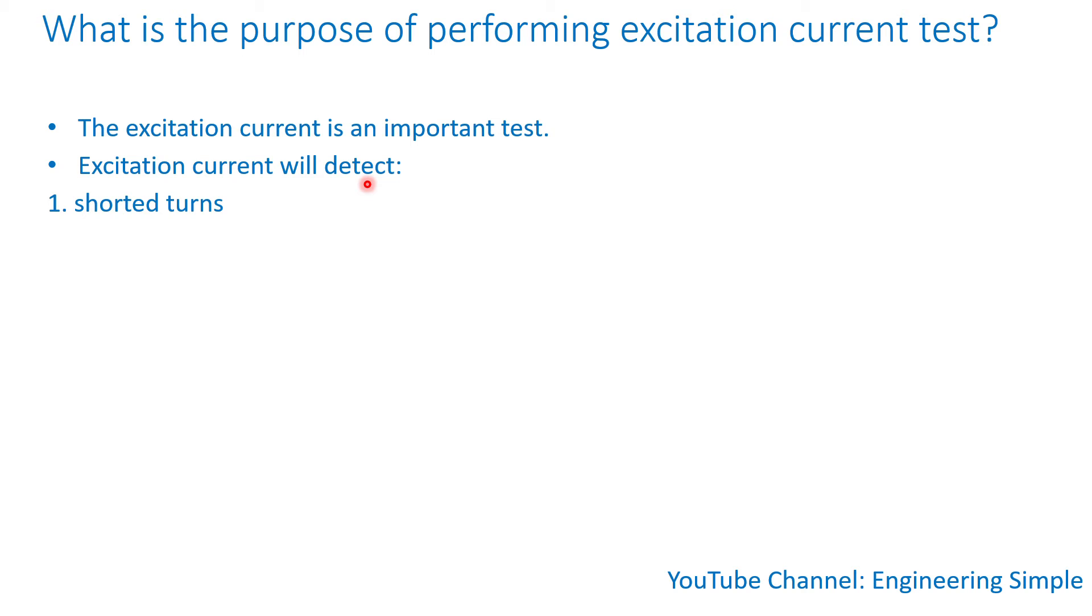The excitation current test will detect a couple of things. If there are shorted turns, it will also detect shorted winding to ground, core lamination insulation damage.